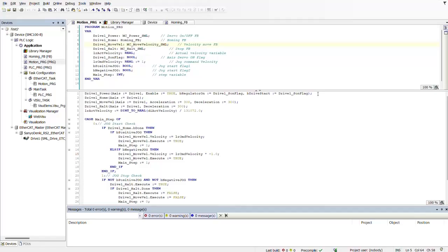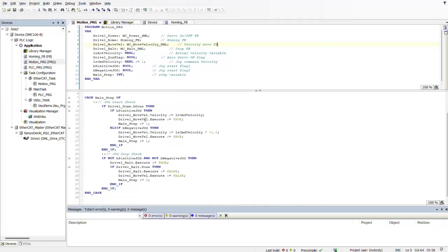Then we have our axis, and this is basically the homing position. We are also adding what type of acceleration and deceleration variables we could have, and we also have our deceleration as well. Lastly, we have the encoder resolution of our motor, which is 131,072 increments. Then we have our flag control — we are able to check when our jog has started and when the jog has stopped. I'm going to include the full programming code in the description below, and this will conclude the software import using our SANMOTION C-S100 Type-B controller. Thank you.